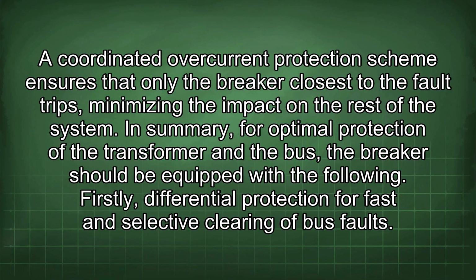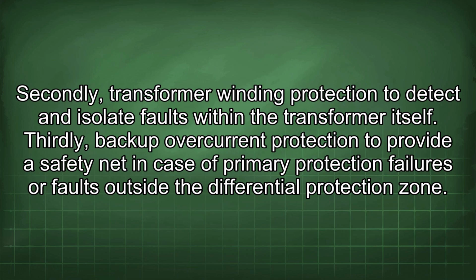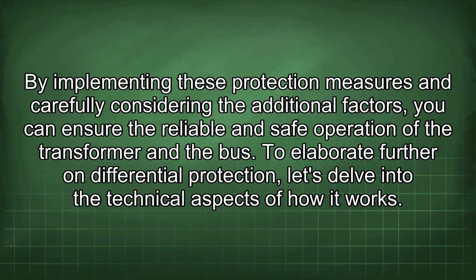In summary, for optimal protection of the transformer and the bus, the breaker should be equipped with the following. Firstly, differential protection for fast and selective clearing of bus faults. Secondly, transformer winding protection to detect and isolate faults within the transformer itself. Thirdly, backup overcurrent protection to provide a safety net in case of primary protection failures or faults outside the differential protection zone. By implementing these protection measures and carefully considering the additional factors, you can ensure the reliable and safe operation of the transformer and the bus.